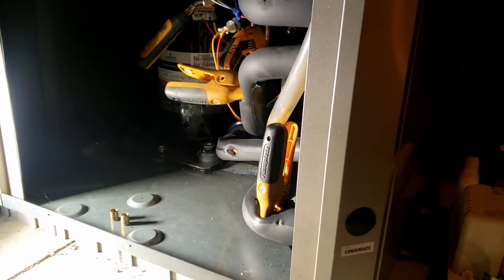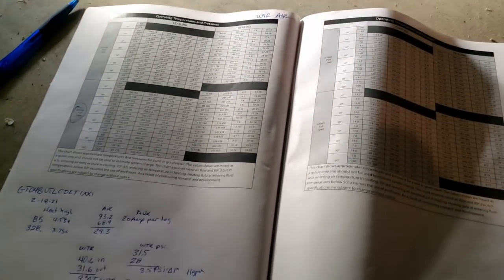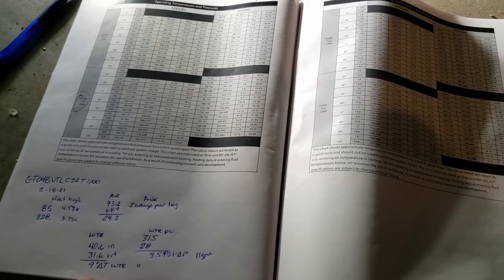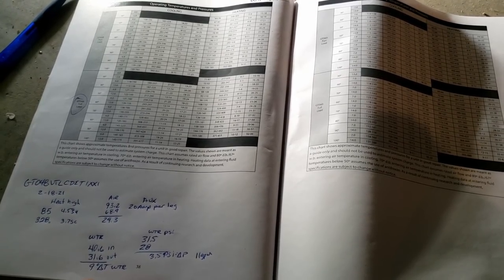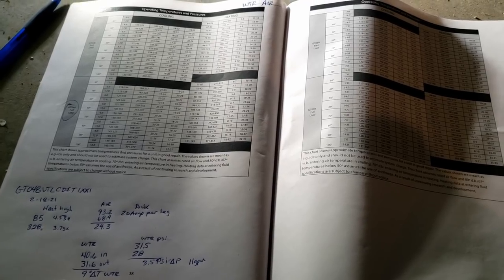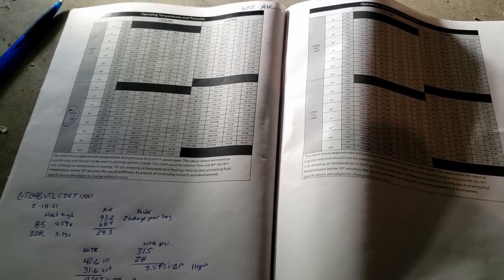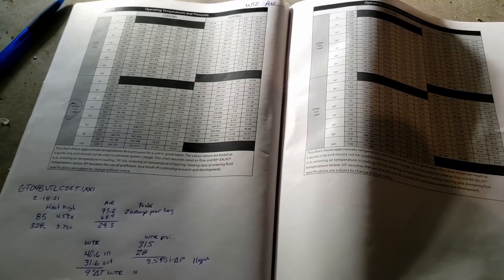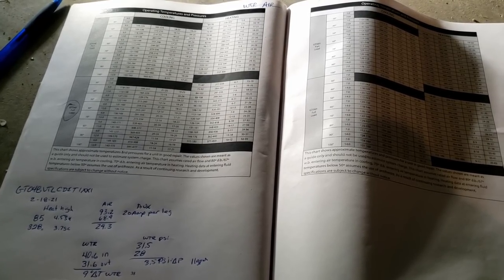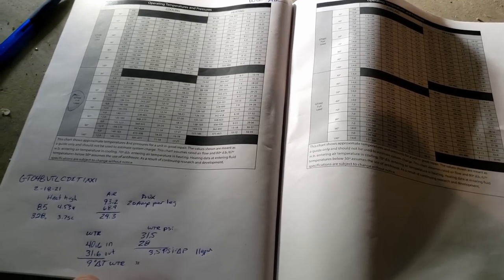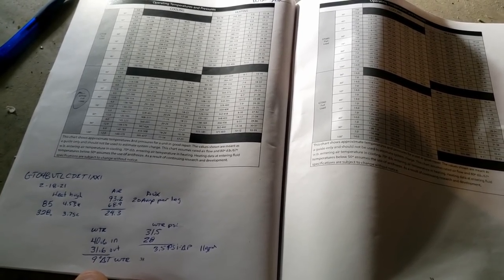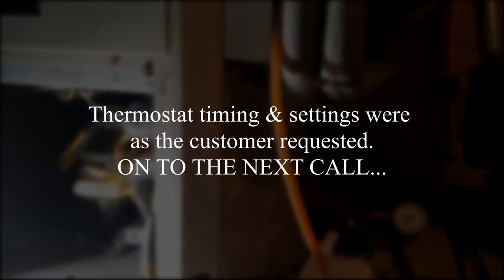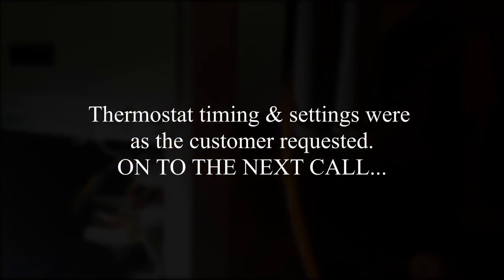I've already done detailed instructions on how to do this in one of my other videos which I can always link up above. So everything seems to be working fine. I'm gonna go up and make sure his wiring is correct and his programming on his thermostat is correct to bring on the auxiliary heat. I just wonder if he's confusing when the blower wasn't running with his problems, or if it's been an ongoing thing. He said it's been running a lot. I wonder if it's an issue with the motor was cutting out or if there's a problem with the auxiliary heat not kicking on when it should. So basically what we're going to do is go up there and double check that and see how that's programmed.